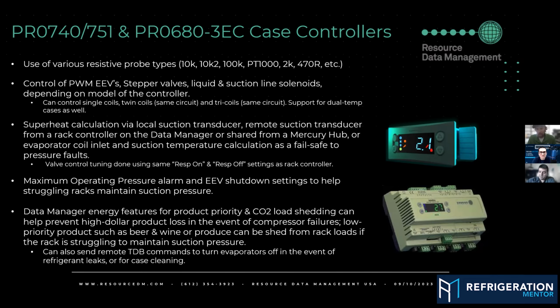We're also going to be looking at some of our case controllers. Case controllers are very similar in that they control a case. That's what they know to do. You can use various different probe types. There's a caveat with any of these controllers. If you're using one probe type, that has to be your probe type for every probe. You shouldn't intermix probes anyway. It's probably a bad idea. You can get all sorts of weird readings going on if you get things crossed.